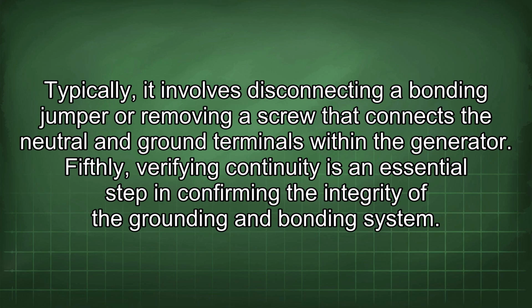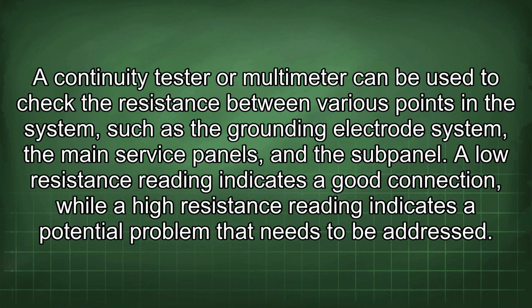Fifthly, verifying continuity is an essential step in confirming the integrity of the grounding and bonding system. A continuity tester or multimeter can be used to check the resistance between various points in the system, such as the grounding electrode system, the main service panels, and the subpanel.